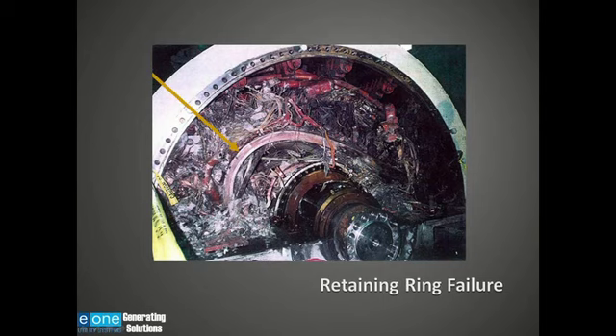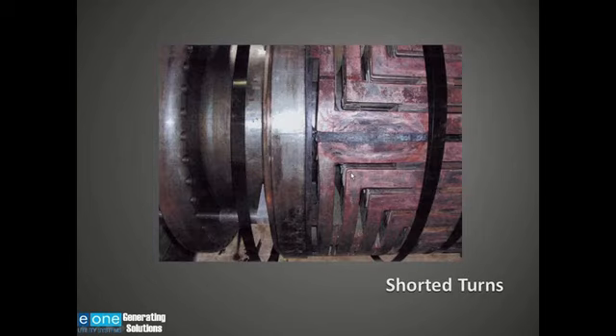This is a picture of the end turns on a rotor with the retaining ring removed. And this is an example of an insulation failure on these turns. Moisture, along with other contaminants, can form a conductive bridge that can lead to electrical tracking or cause insulation to deteriorate and cause a coil-to-coil short. There's a great paper that was written by the late Don Albright, founder of Generator Tech, that discusses insulation failure in detail.